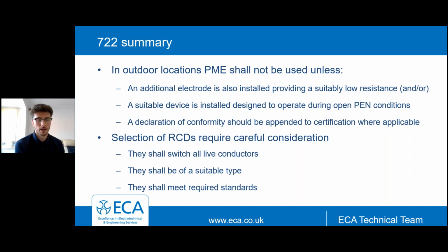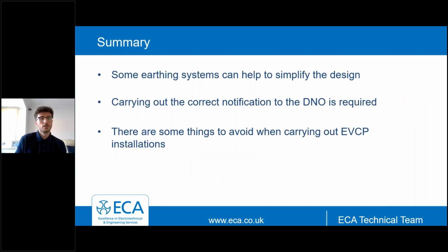information obtained as required. We also looked at RCDs, and the selection of RCDs for EV charge point equipment requires careful consideration. They shall switch all live conductors, they shall be of a suitable type, and they shall meet required standards. We also looked at some other earthing systems, and this may help to simplify the design when not having PME systems that are for use outdoors.